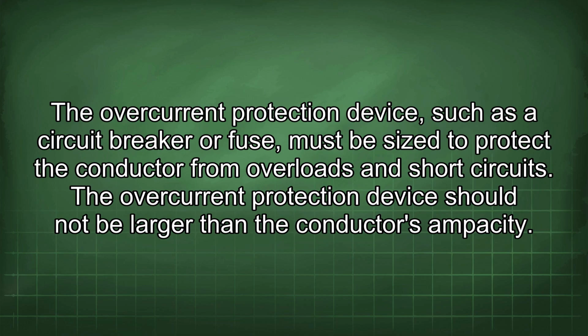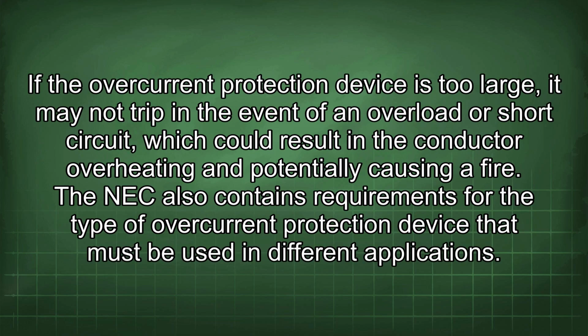The overcurrent protection device, such as a circuit breaker or fuse, must be sized to protect the conductor from overloads and short circuits. The overcurrent protection device should not be larger than the conductor's ampacity. If the overcurrent protection device is too large, it may not trip in the event of an overload or short circuit, which could result in the conductor overheating and potentially causing a fire.